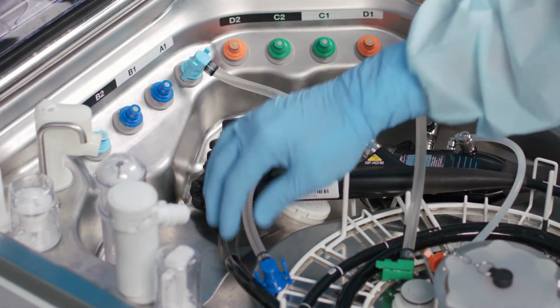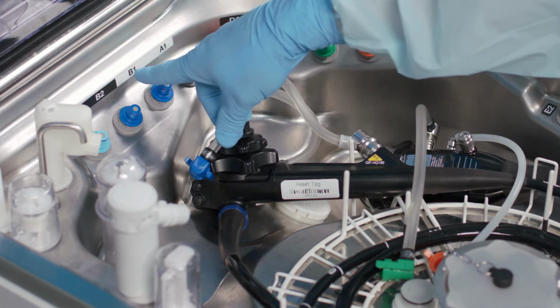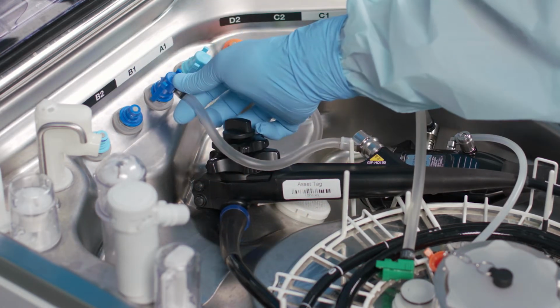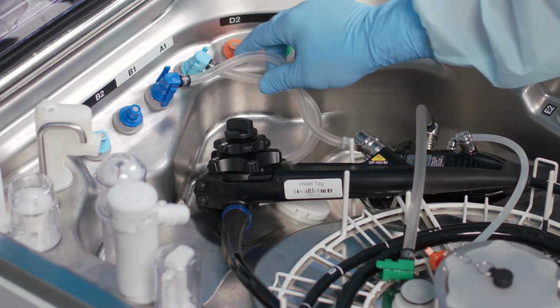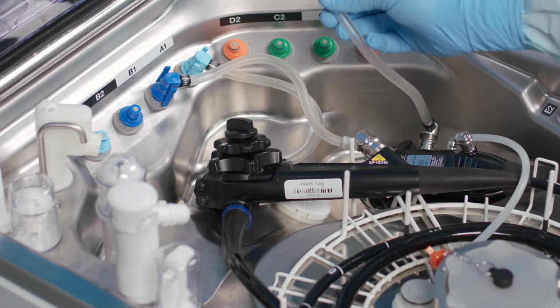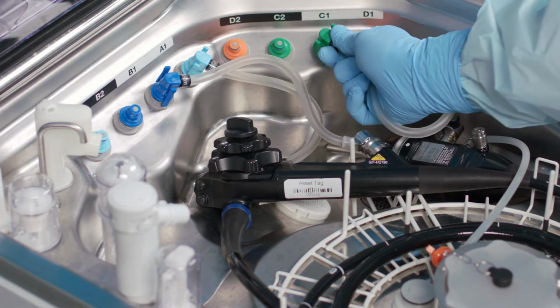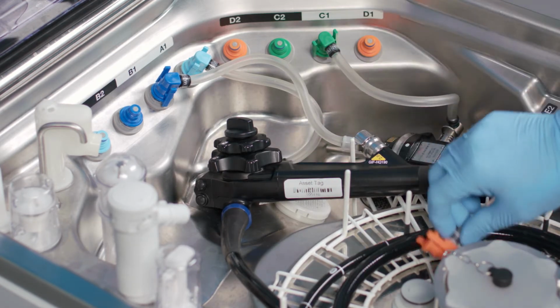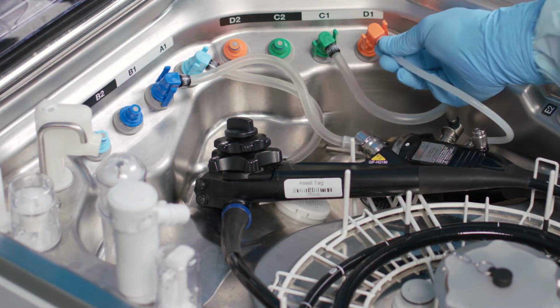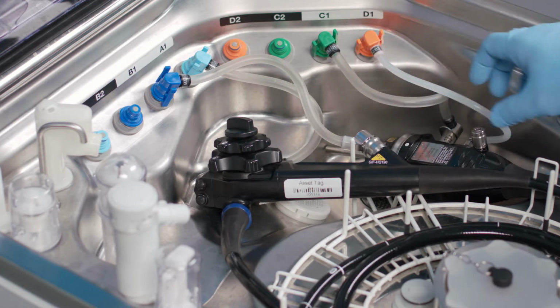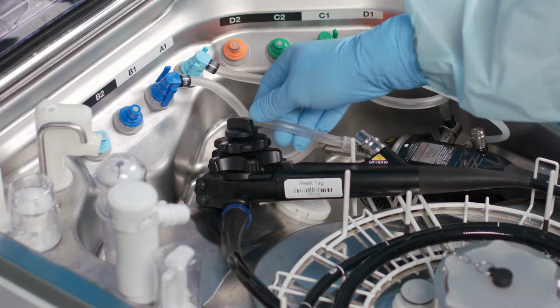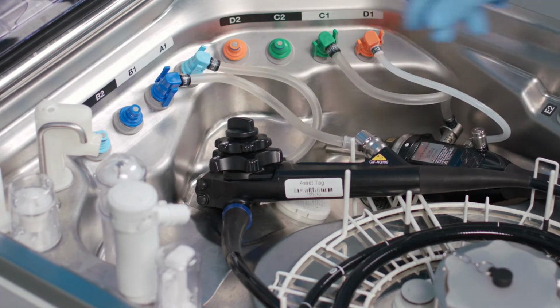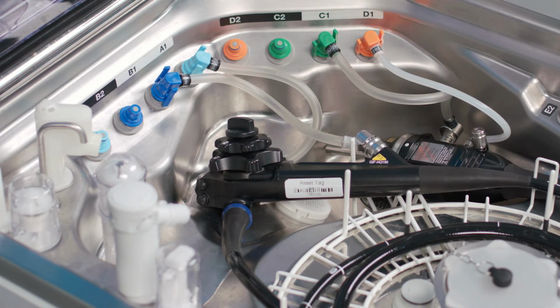If the connecting tube is connected to the wrong connector, for example, the connecting tube for the first endoscope is connected to the connector of the second endoscope, then channel blockage monitoring and channel connectivity monitoring cannot work properly. It's important that none of the connecting tubes are kinked. At this point, any unnecessary tubes should be removed.